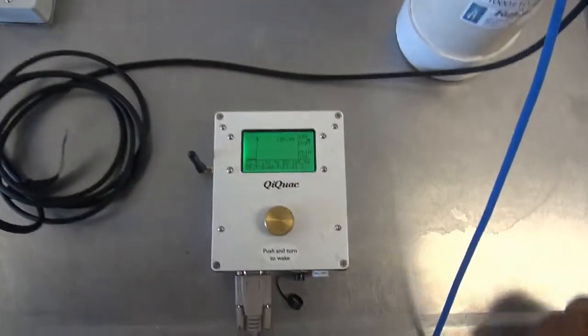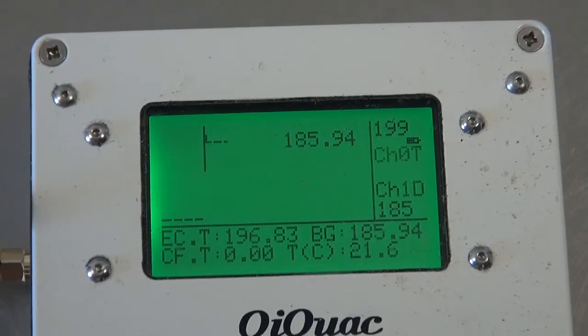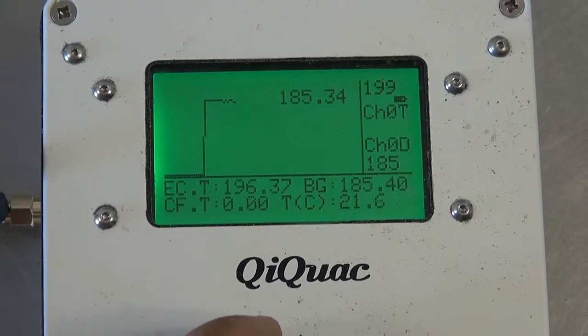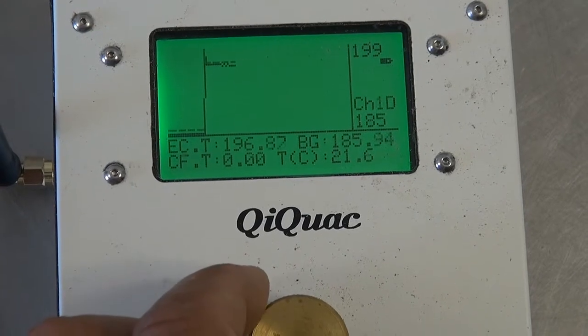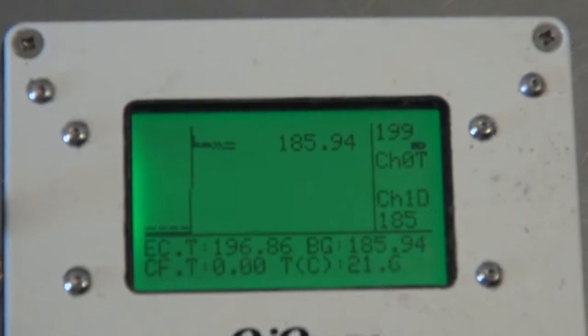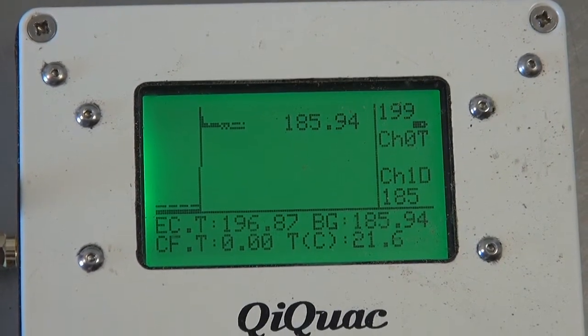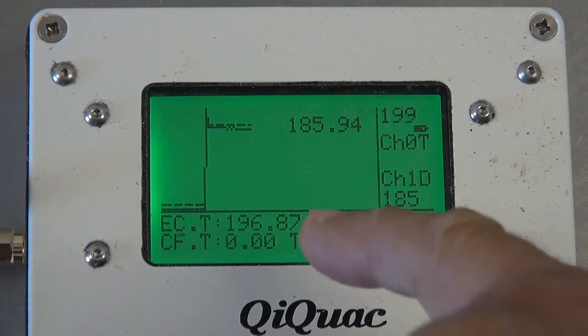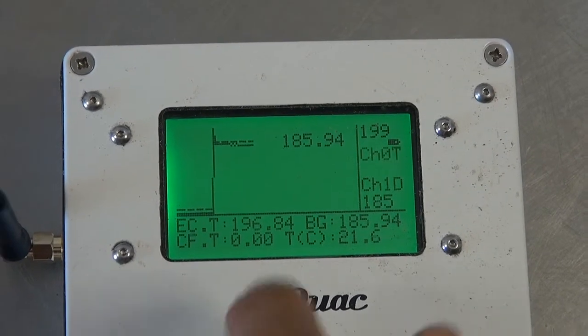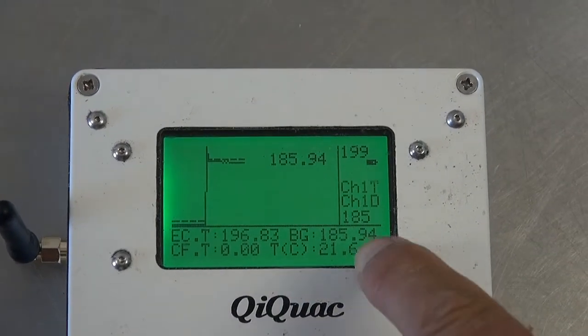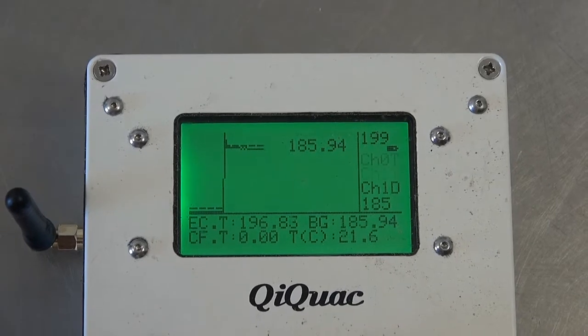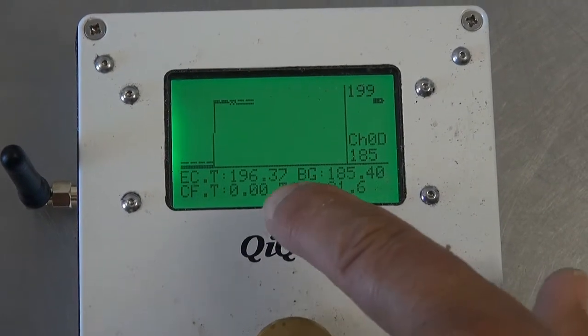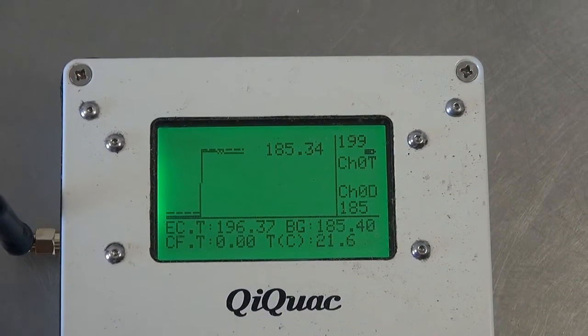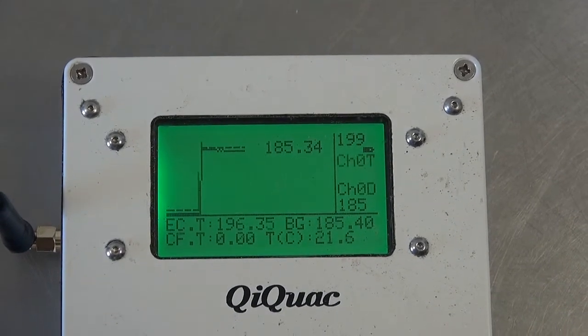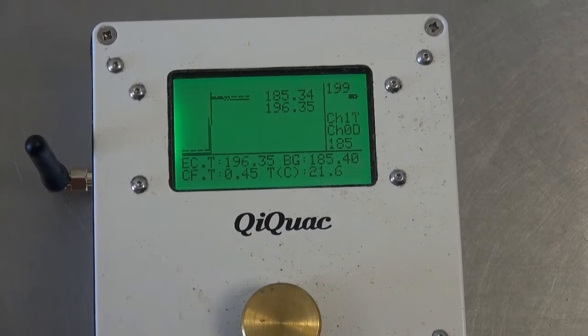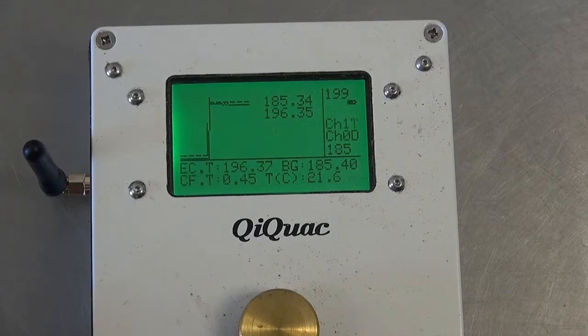And you can see here, the graph has just picked up the change in conductivity. There's one probe there, you can see it's a solid line. And there's the other probe there, the dotted line. You can see them up top now. Now, we don't have another reading up top displayed because we haven't accepted this value. You can though see the value there, 196.84 on the first line of values, and you can see the BG, the background, 185.94. If we toggle back one, we've got 196.37 and 185.40. So we'll accept those values by pushing the knob down, and you can see now it's logged that value.